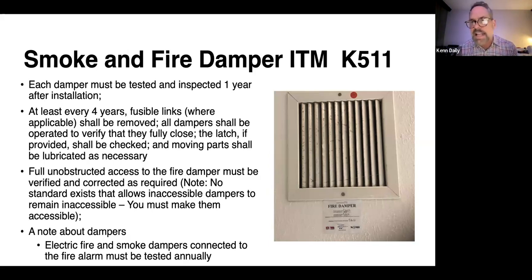So they should also be functionally tested annually, because that's all part of your shunt trip on your HVAC when the fire alarm goes off. If you have smoke dampers, your air flow stops. A fire damper is typically a non-electric device. It's a fusible link in the chain, and if that fusible link reaches critical temperature, a lot of times it's 135, it melts, and then that damper closes. But again, you're inspecting, testing, and maintaining these every 4 years. That's why it's so important to know where these are located. Access to these is required, and then inspection, testing, and maintenance is expected, and then documented every 4 years.